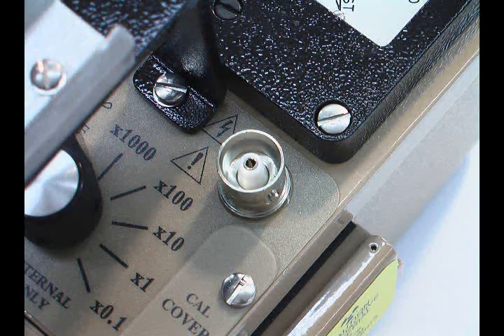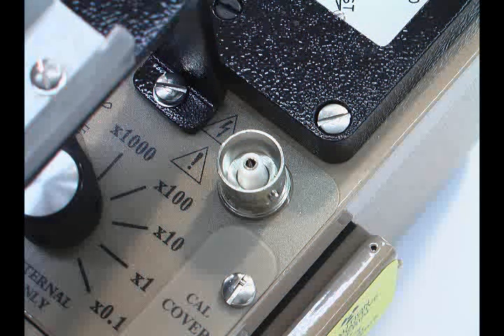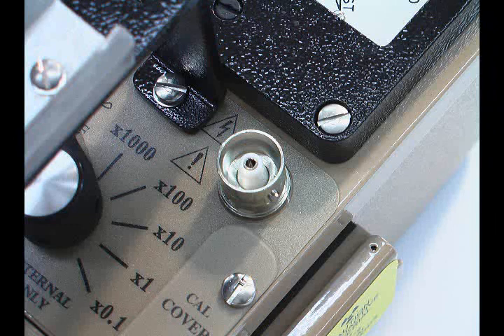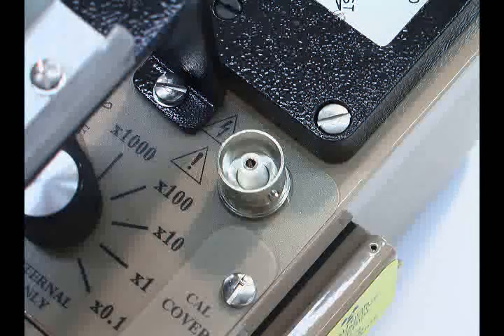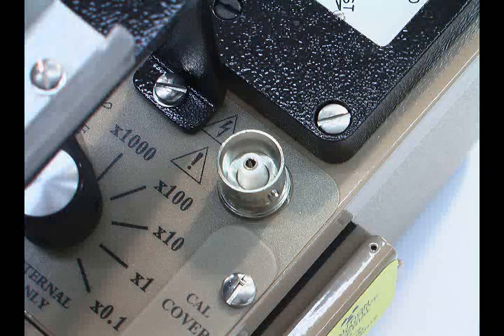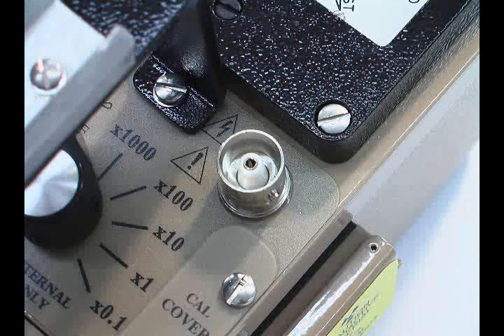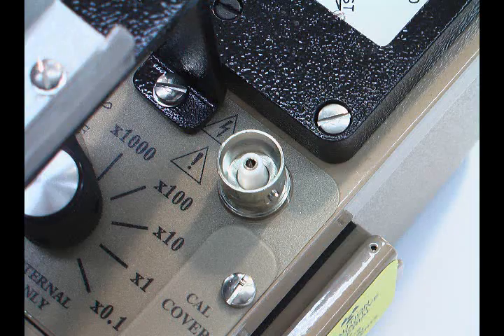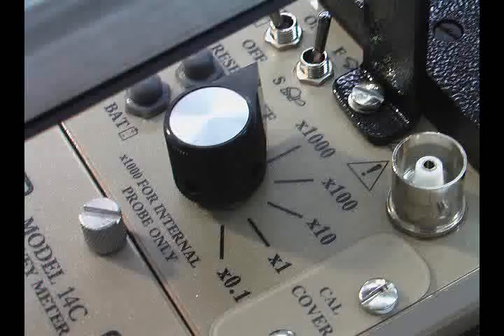There is a connector used to connect the detector to the instrument with a coaxial cable. The detector operating voltage is supplied to the detector via the detector input connector. A mild electric shock may occur if you make contact with the center pin of the input connector. Switch the Model 14C range selector switch to the off position before connecting or disconnecting the cable or detector.